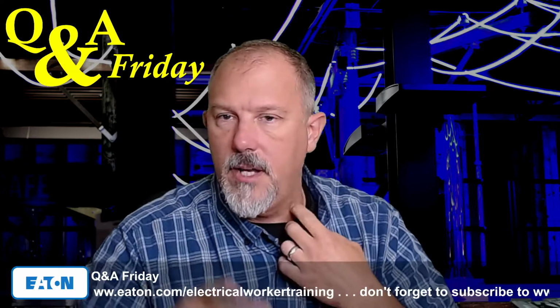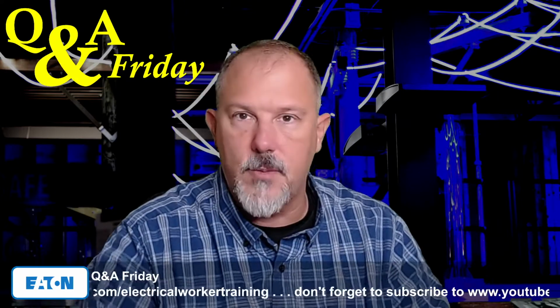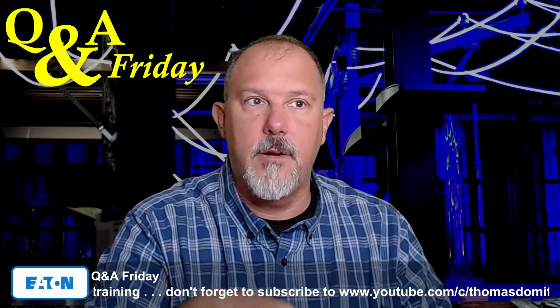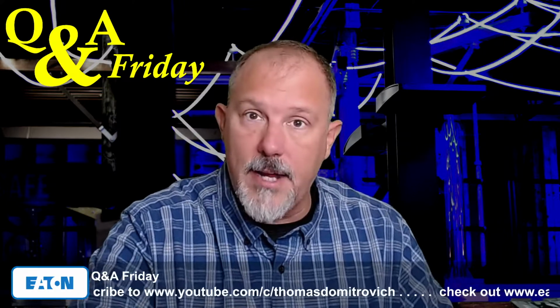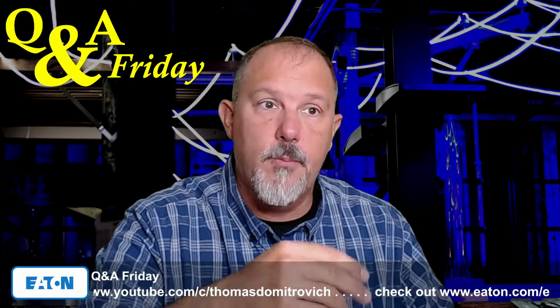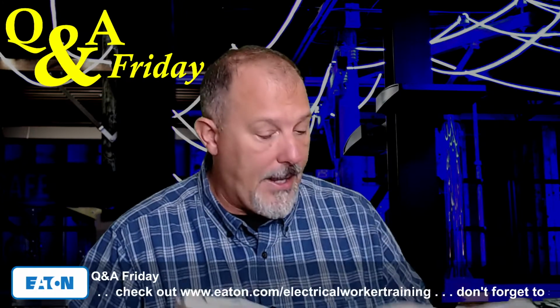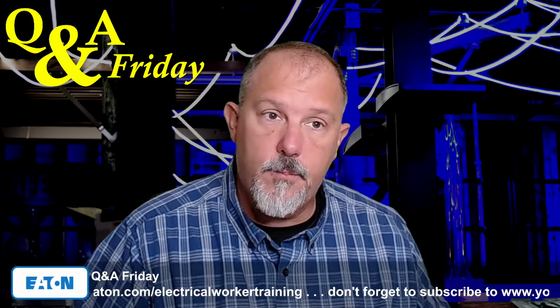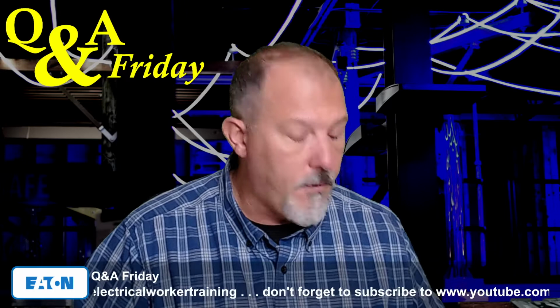And if you have the bodies of water reference, I'd appreciate that, so we can take a look at that language that you're saying, that their intention is to have it ahead. But I think you bring up a really good point, that we really have to look at when we say provided for, as opposed to the language that we find in 210.8(A) that says shall have ground-fault protection for personnel.